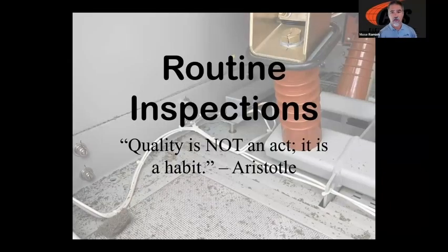So let's get started. Quality is not an act, it is a habit. This is from Aristotle. This is about whatever the daily, weekly, monthly tasks are that you're doing to ensure the safety and the reliability of your substation. Little things, like in the background picture here: are your filters in good condition? Are we keeping the bugs and the dirt and the grime as much as possible out of our gear? And are our heaters working?